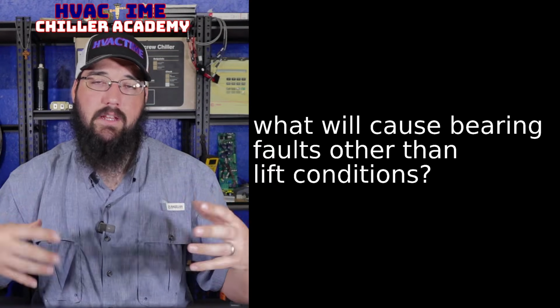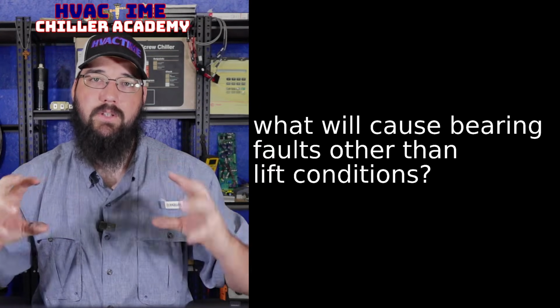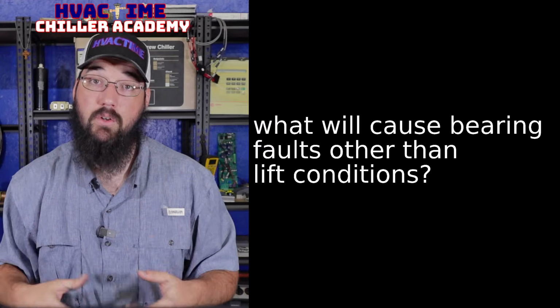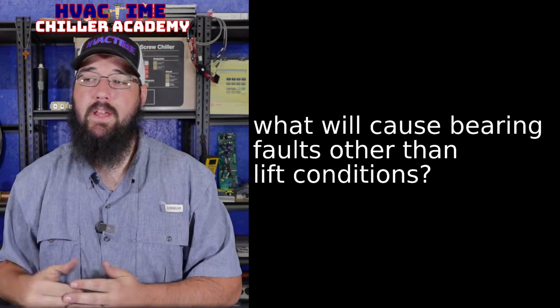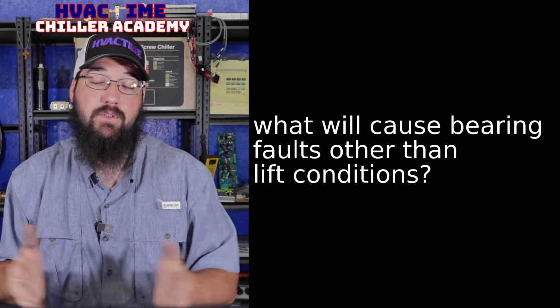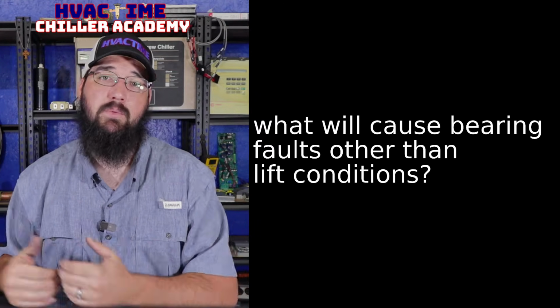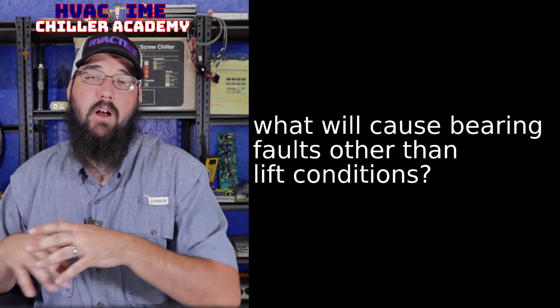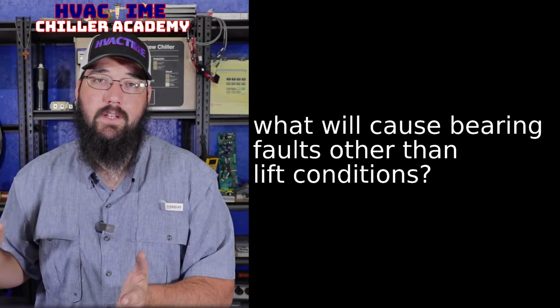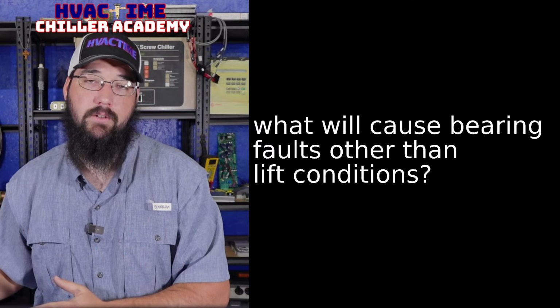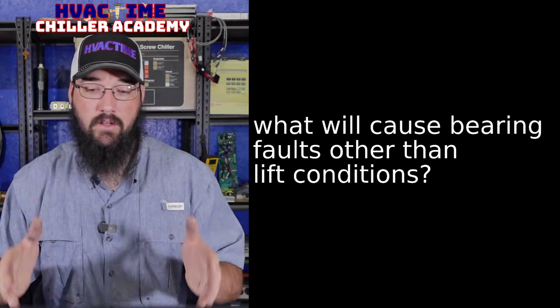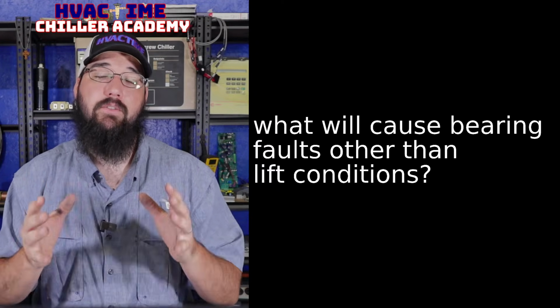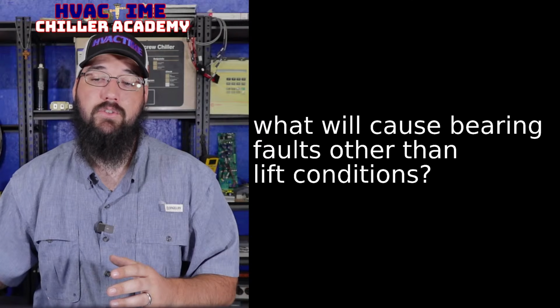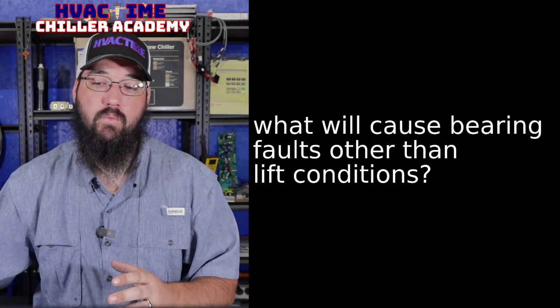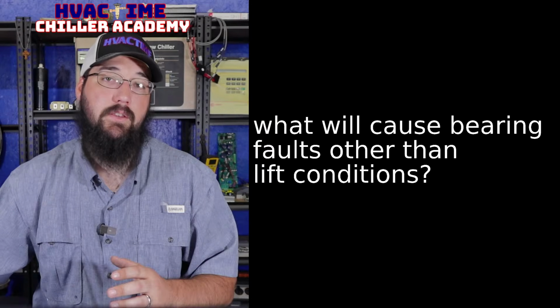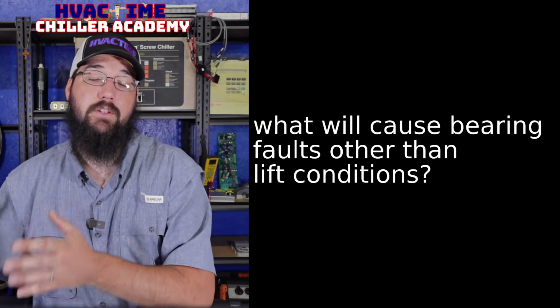If the shaft itself begins to demagnetize, that's going to result in a bunch of bearing faults. And the thing is, if that happens, you're still talking about a compressor. So there's been plenty of times where, out of all your options here, the one that doesn't mean a new compressor is the inverter. And there is not a solid way to verify one way or the other without just trying to replace the inverter, right? So you're going to have scenarios where it just might make the most sense.